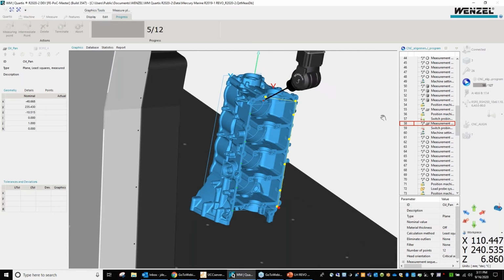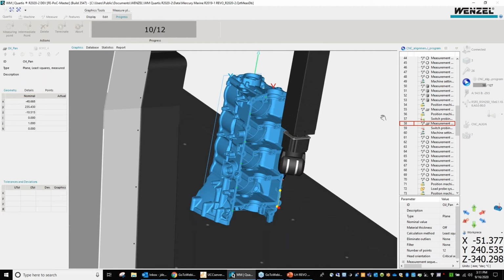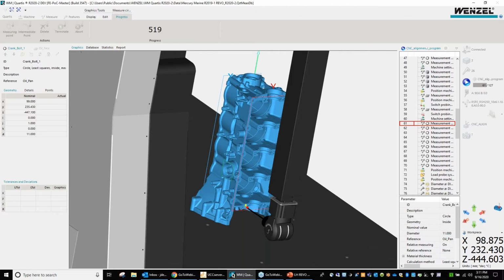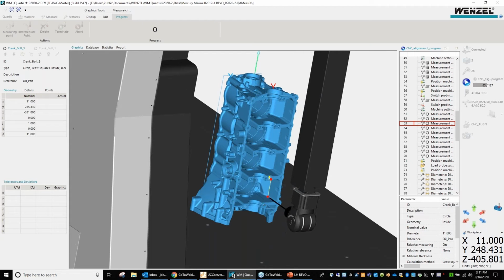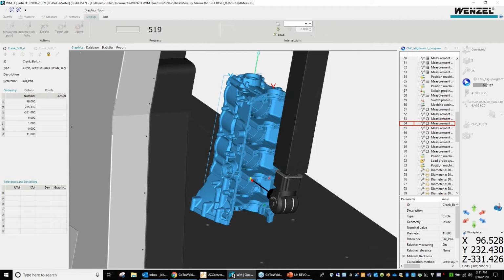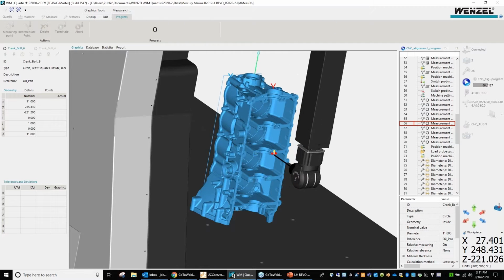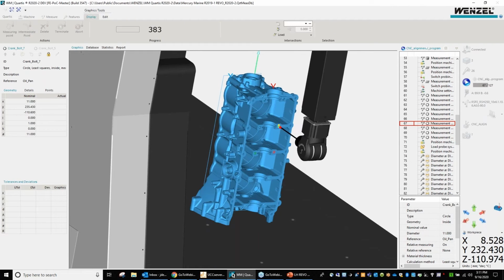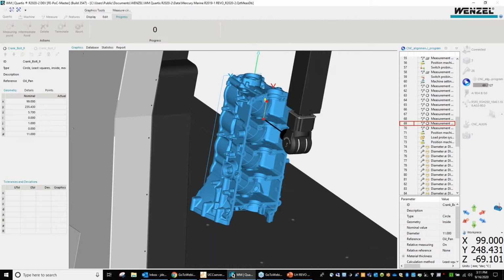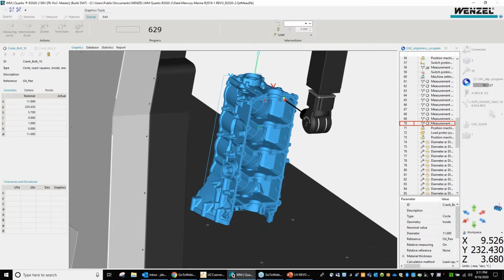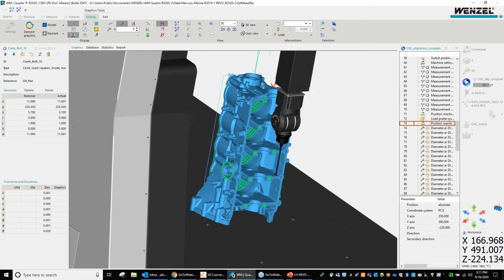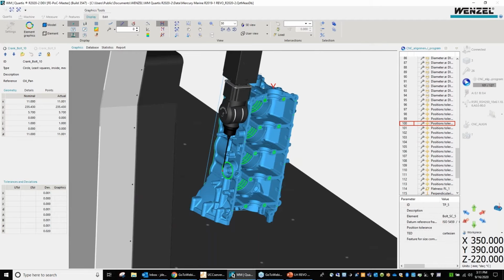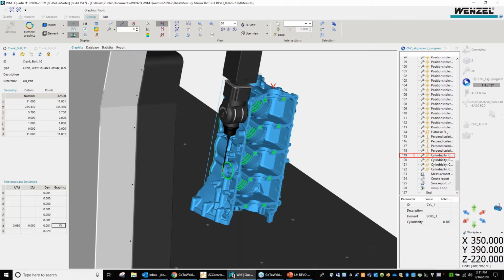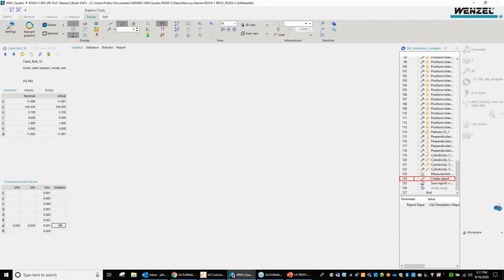Now, not only can it scan, but it can also take touch trigger points. So what it's doing here, it's moving the carriage and flicking the head at a head motion to do head touches for individual point measurements. So the A and B angle that you see of the probe head, your B is your clocking around from 0 to 360 degrees, and your A is currently sitting at 0, 0 right now, but it can go all the way up to 120 degrees up in A. So if you need to get up underneath a part, the Revo is a great tool to do that.